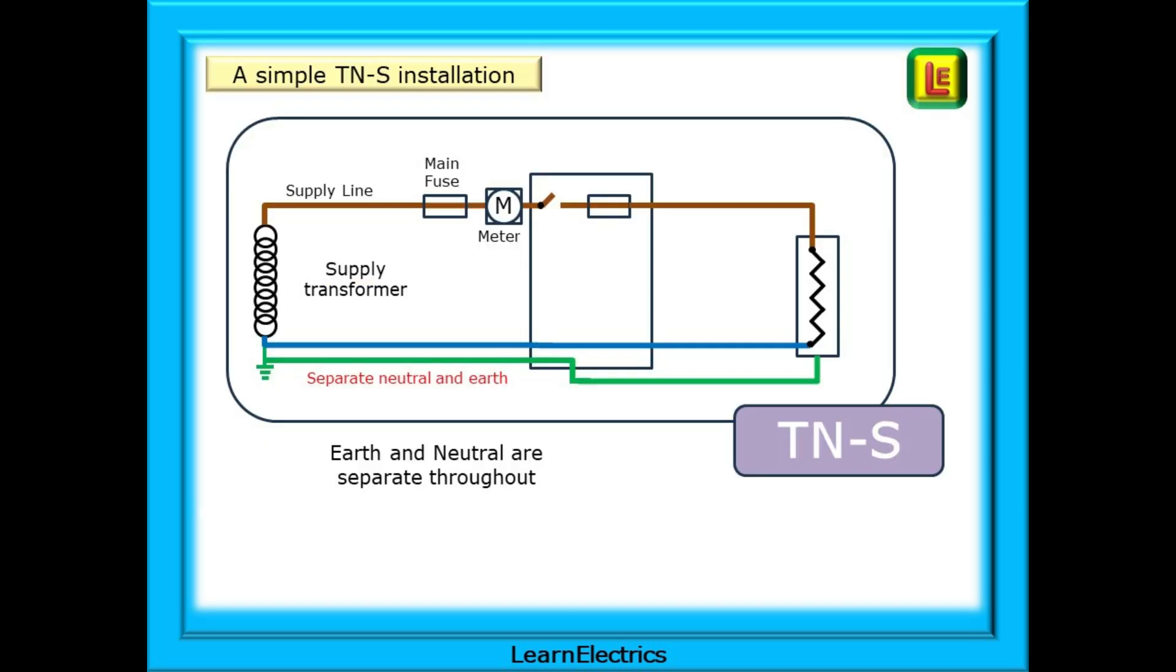We should remind ourselves of what is involved in an installation. Looking at the outside world first we will use a TNS system. TNS stands for earth and neutral separate throughout the system and you can see here that the neutral and earth conductors are joined at the supply transformer but once they leave the transformer they are separate throughout the installation.